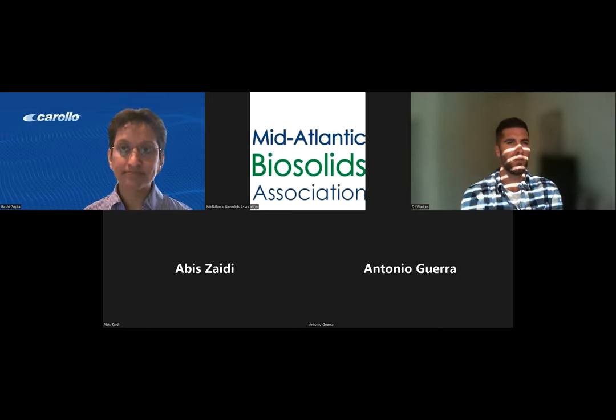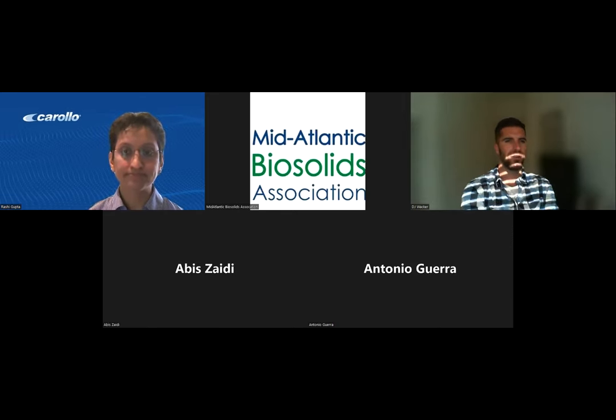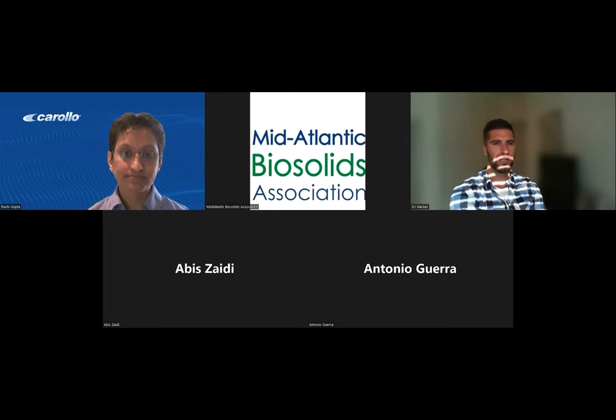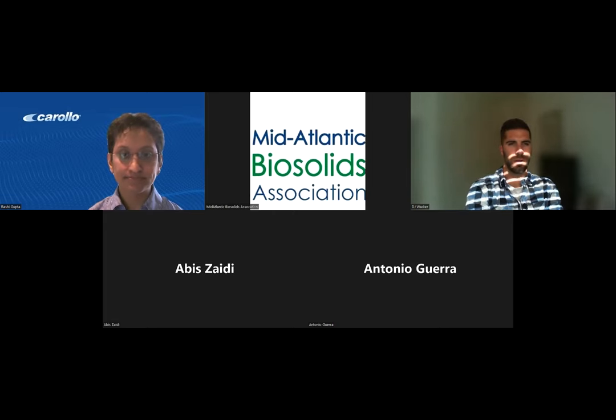So this is a good question from a practical sense of flow-paced auto control: what if the characteristics of the sludges change, such as biopolymers, colloidal content, et cetera? How does the system react to this inherent change in the sludge going to the dewatering besides flow? So if you answered this, Tony, but if you want to elaborate, that'd also be good.